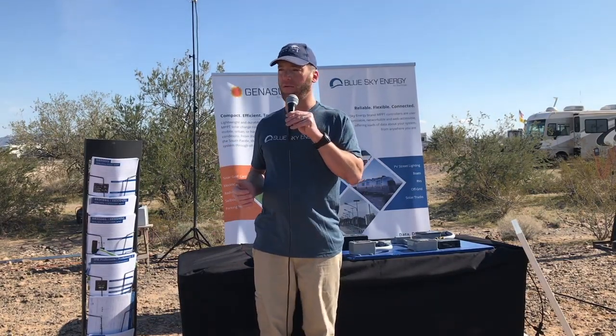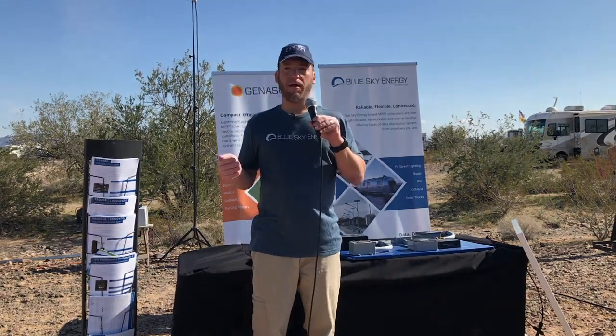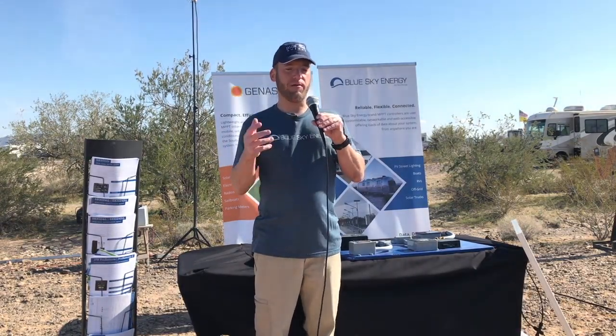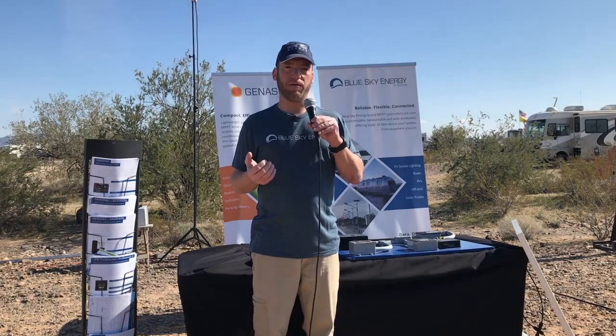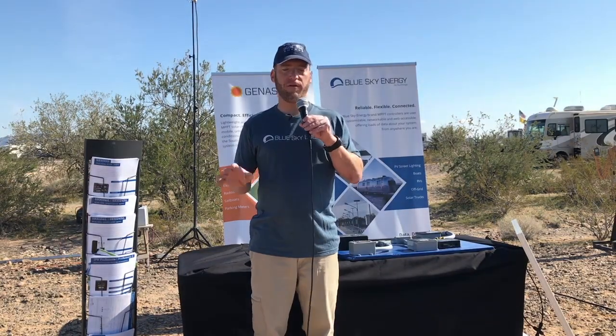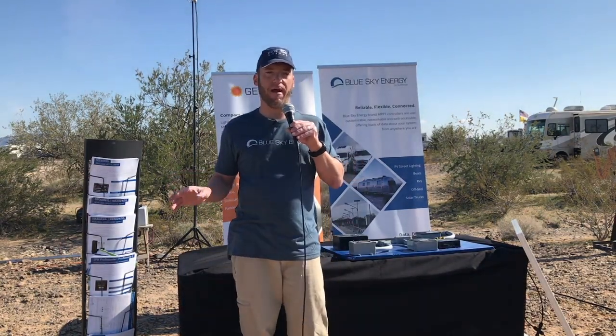I also wanted to cover troubleshooting. Fuse holders are one issue, but another time, let's say somebody calls me up and says their controller is no longer charging, or it's charging at a much less than expected rate - the first thing I'll have them do is look at the input voltage. Generally speaking, your input voltage should never be below 15, I don't care what kind of panel you have.